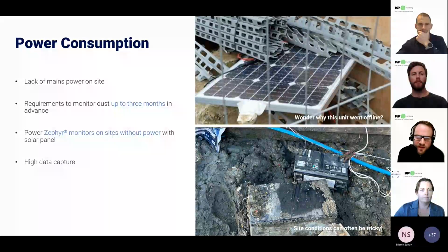So until now, we have been extremely reluctant to run our dust monitors using off-grid power, as the power required to run pumps, lasers, and heating elements is too much to reliably run them, either on batteries or solar.